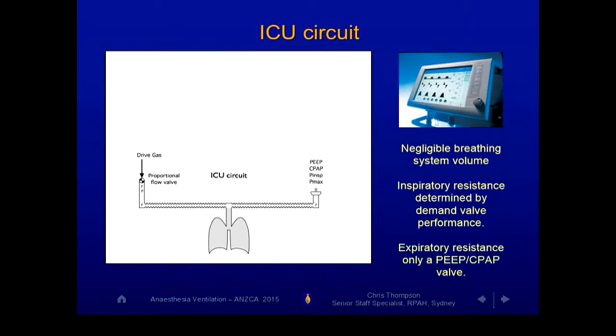Okay, so now let's look at the thing that's made it all different, is that we've got machines now that we can recruit with, we can use pressure support on induction, and often people don't understand what's different about them inside. And this is true for a Dräger machine, so this is not true for a GE machine or a Mindray machine. They've done something which I think is very clever. So here's a picture of an ICU circuit. On the left, there's a way to push gas in when you need to, and on the right, there's a PEEP valve. So I haven't got a laser pointer, but basically when you breathe in, they drive gas in and close the PEEP valve a bit. Air comes into the patient. When you want to exhale, they release the PEEP valve to your PEEP value and stop pushing it in, and you exhale. There's not much dead space in that circuit. There's not a lot of pressurizable volume. There's no inefficiency because all your gas goes out.